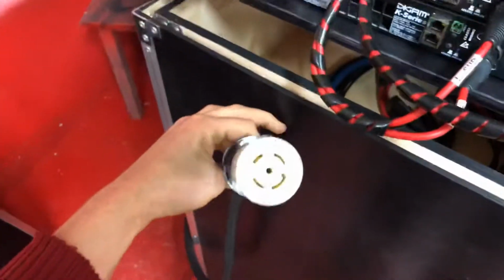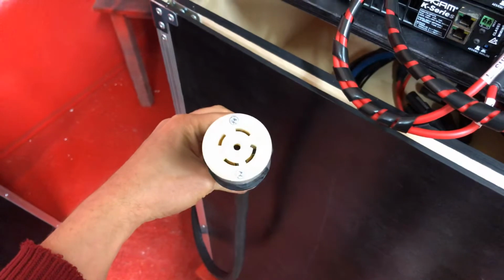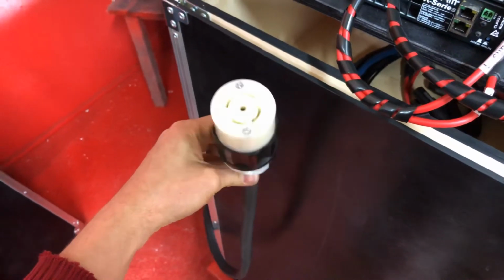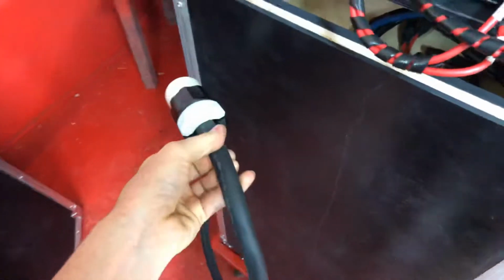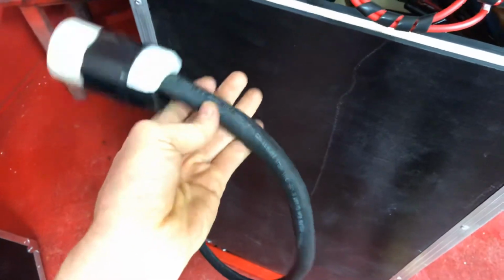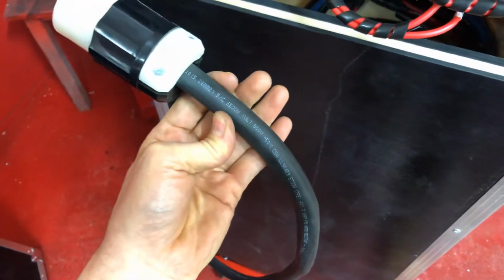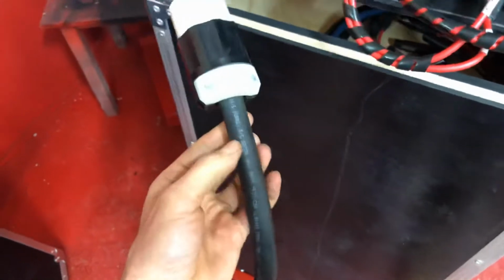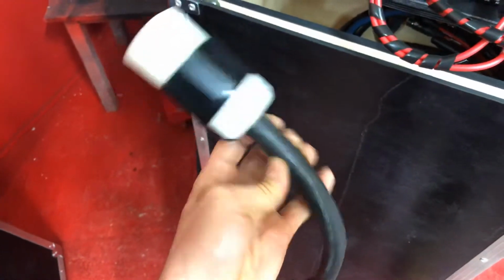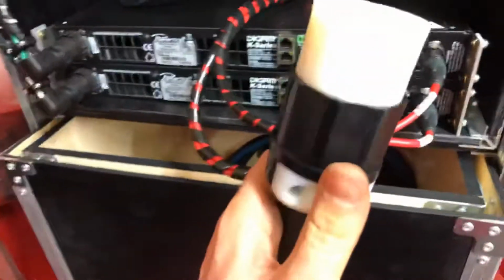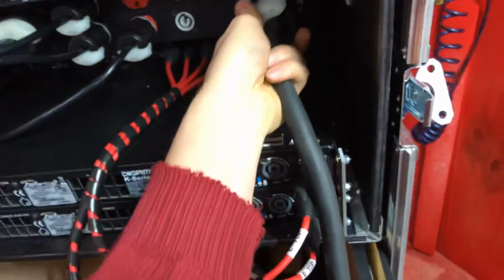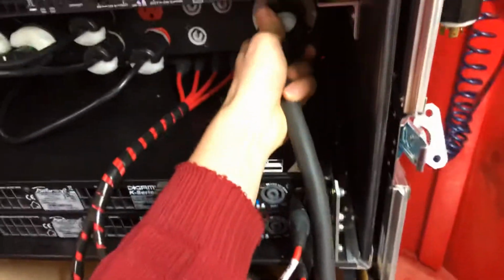That'll power here, and I'll have my L21-30 3-phase input here, which is, of course, 3 hots, a neutral, and a ground center pin, and a 10-gauge cable. I like the SEOOW cable standard. The SOOW has a smell to it, and I don't like the smell. So again, this is a 3-phase twist lock here.